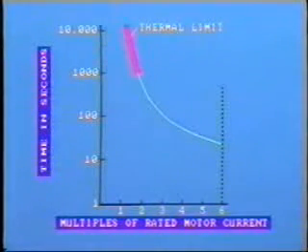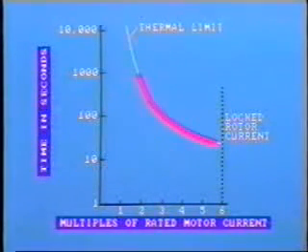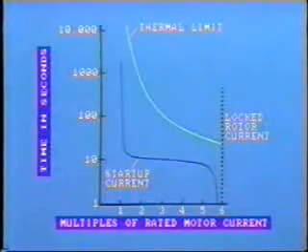The thermal limit curve is actually a composite of several undesirable conditions. The upper portion shows limits of overload when the motor is in operation. The lower limit shows the locked rotor condition, that is, the magnitude of current and its allowable time limit. The center portion of the curve shows the current limits that are recommended while the motor is running up to speed. We can also show on this same diagram the curve that represents the stator current during startup.